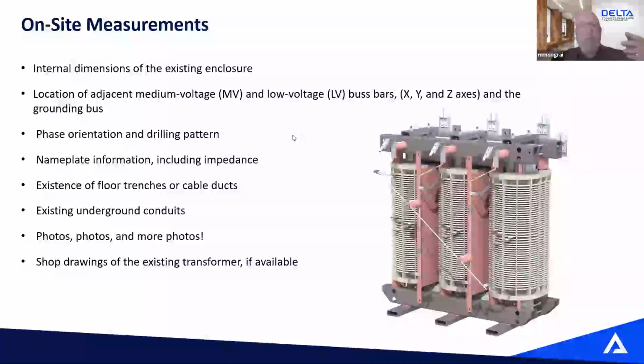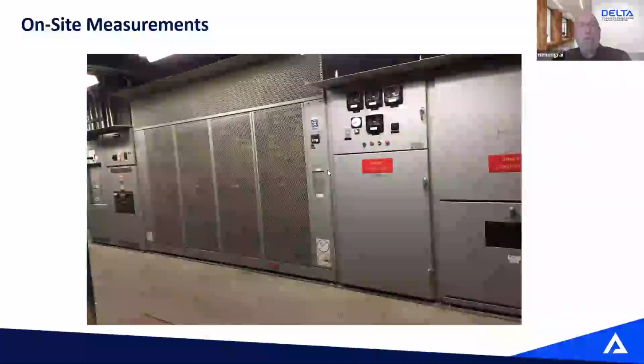We need the phase orientation. We need the drill pattern. We need the nameplate information. Where we mount the transformer, on the housekeeping pad or on the floor, we need to know if there are trenches, cable ducts, any conduits. We need lots and lots and lots of pictures, and ideally, if it's available, the shop drawing of the existing equipment.